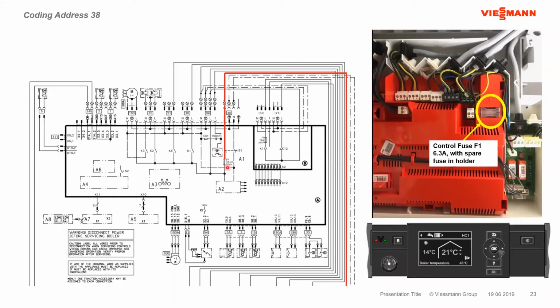But that's basically sitting right there. So once the power's on, we go through that fuse, and now, again, that line voltage is basically idling, sitting there waiting for these relays here to close, and they're going to close as a function typically of boiler operation. So the pumps will operate based on load and demand, your domestic pump and your boiler pumps, for instance here.